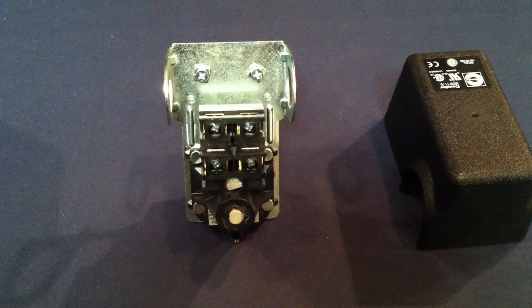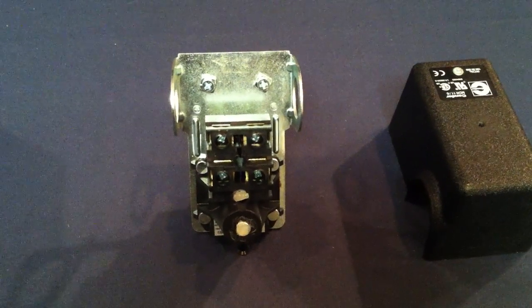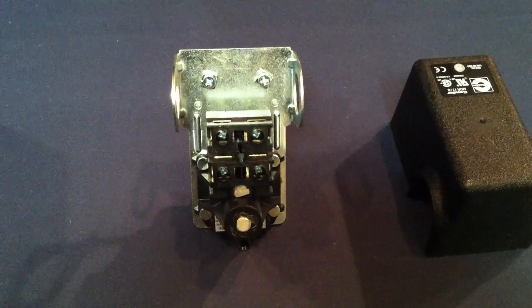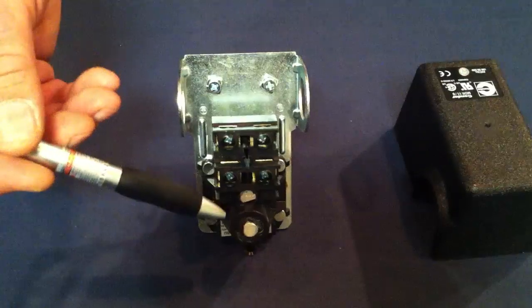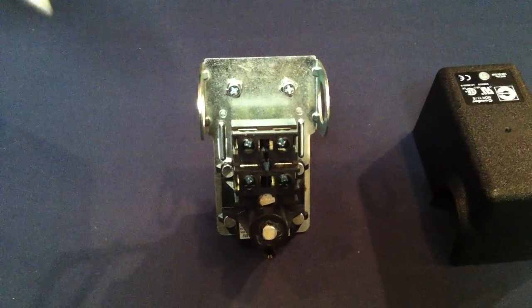The riser mounted compressors are good up to 50 pounds. So if you need to adjust this, the screw that you're going to look to adjust is this one that sits up top here. It'll be in the instructions or you can call us.